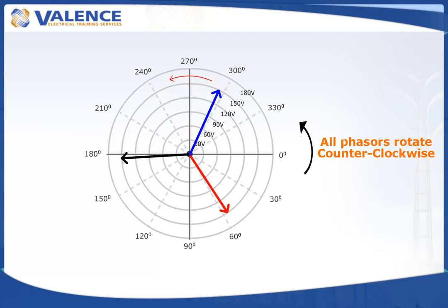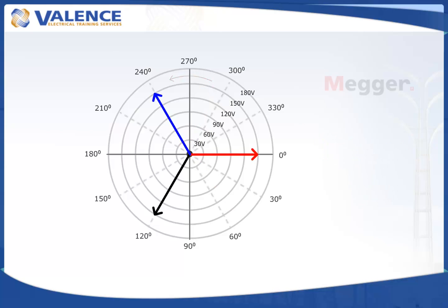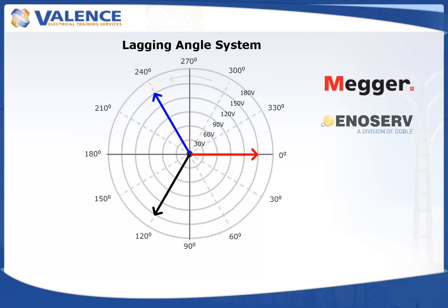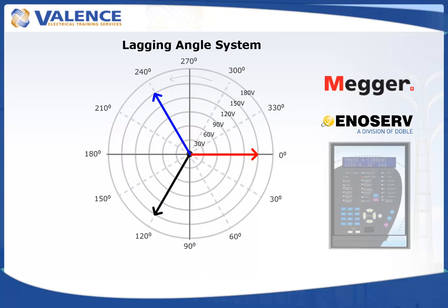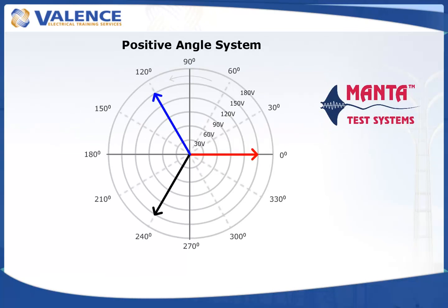The previous examples showed the system used by Megger test sets, ENOSERV RTS software, and GE SR relays. Here's how you would draw the same phasor using test sets from Manta test systems and DOBLE. Notice that the angles have the same 0 to 360 degree reference, but they're drawn in the opposite direction.